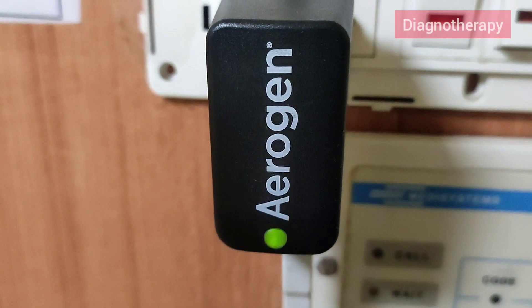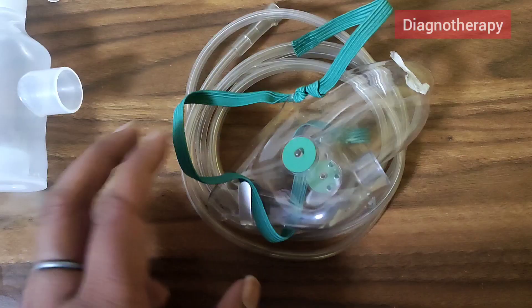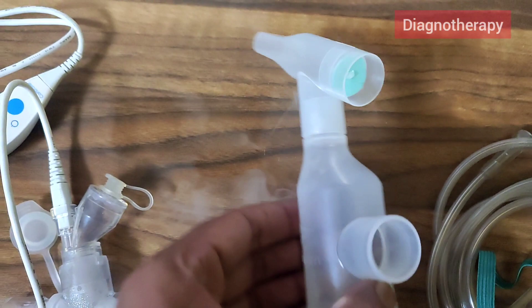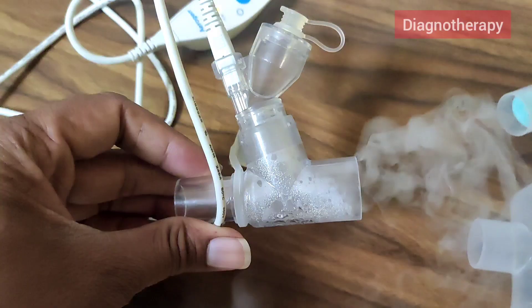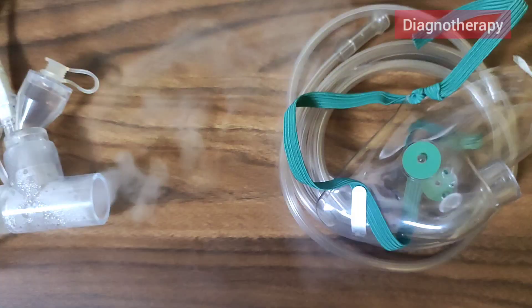Now we will be seeing a few accessories of this nebulizer. It can be used through a mask or directly from the mouth with this attachment. In the back, there is one attachment for oxygen, and this is the intermediate connector if the patient is on a ventilator or if any other attachment is needed. The delivery of medication through this principle is very effective, as there is a very dense fume and no change in temperature when the liquid converts into aerosol.